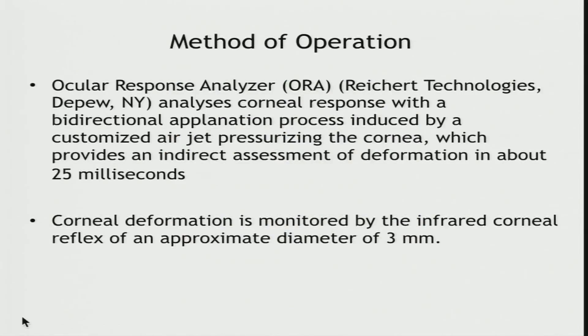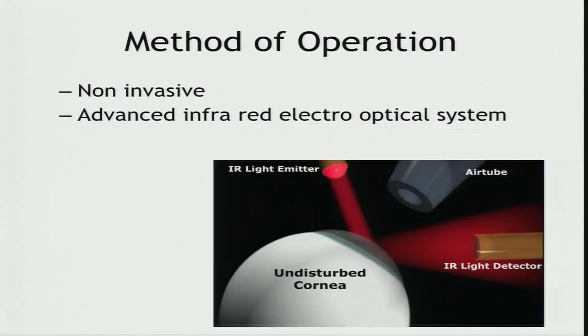This is a picture of the ORA. It analyzes the corneal response with a bi-directional applanation process induced by a customized air jet pressurizing the cornea, which provides an indirect assessment of the deformation in about 25 milliseconds or so. The corneal deformation is monitored by the infrared corneal reflex of an approximate diameter of 3 millimeters.